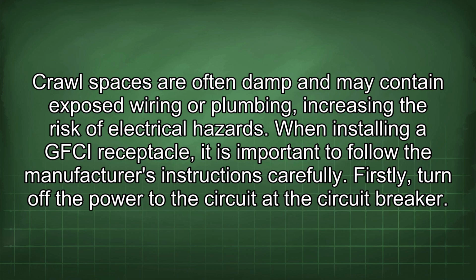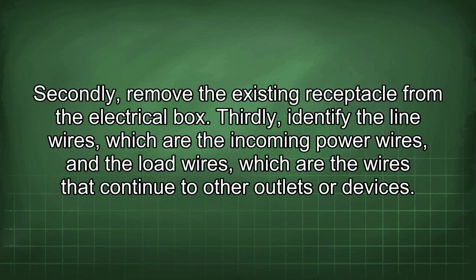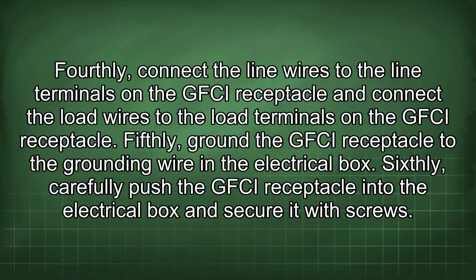When installing a GFCI receptacle, it is important to follow the manufacturer's instructions carefully. Firstly, turn off the power to the circuit at the circuit breaker. Secondly, remove the existing receptacle from the electrical box. Thirdly, identify the line wires, which are the incoming power wires, and the load wires, which are the wires that continue to other outlets or devices. Fourthly, connect the line wires to the line terminals on the GFCI receptacle and connect the load wires to the load terminals on the GFCI receptacle.